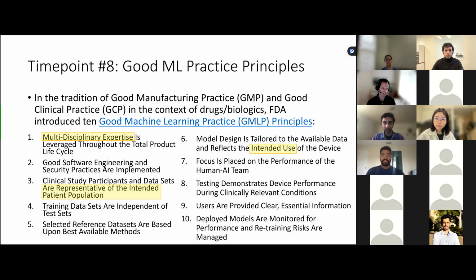So it's at least good to be thinking through probably not just complying with intended use, but likely foreseeable use. And this happens all the time in the healthcare space, where my user is not going to use it exactly as it's supposed to be used. They're going to tweak it, or they're going to do a little something with it. And might that misuse result in harm? If so, you could be in trouble. So you want to have that front of mind.